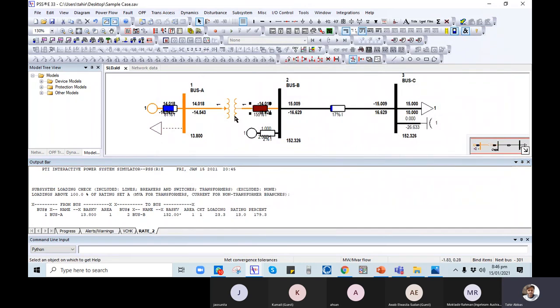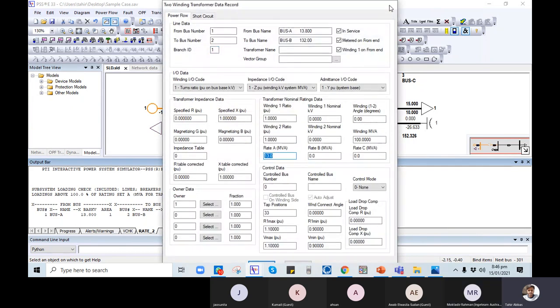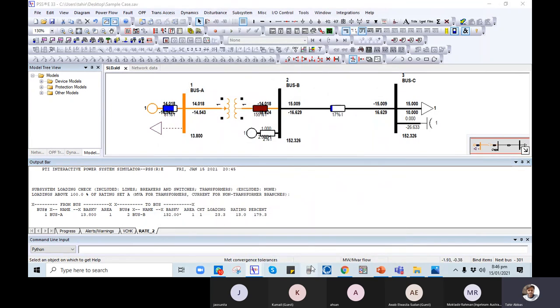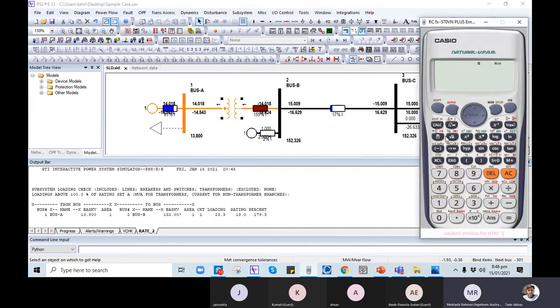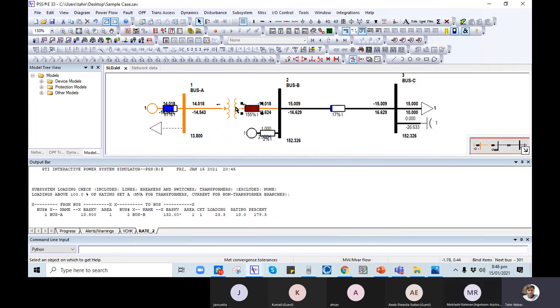So this transformer, okay? From bus 1 to bus 2, there is a transformer, because the value is 13 MVA, okay? And the passing MVA, I can calculate in front of you: 14 squared, that is P, plus 14 squared, that is Q, and under root, this is S. Now you can see this is 19. And the value set in the transformer is 13. So 19 divided by 13, you can see 152%, 155. Here you see 155. Can you see?